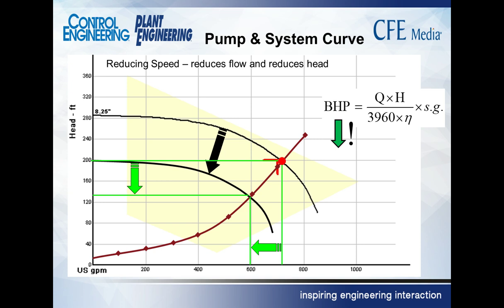This is what you get when you change the speed of the pump. You reduce the speed of the pump. So what happens to head and what happens to flow? They both go down. Well, if the horsepower is flow times head and they both go down, what do we know has to happen with the power? It has to go down. If we reduce the amount of power that's required, we will save the energy that would have been used by throttling the pump instead. Any questions on that?